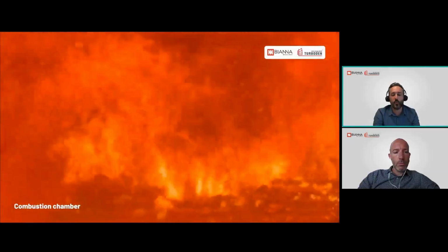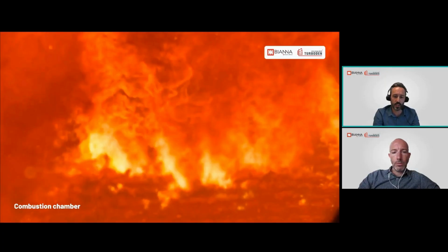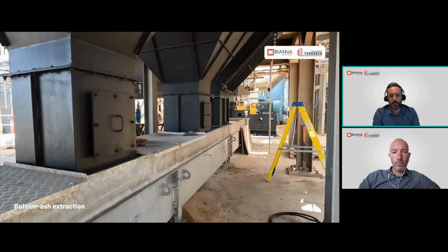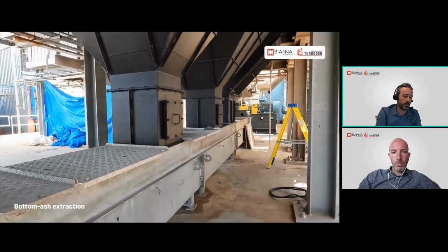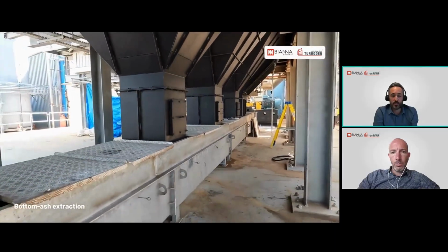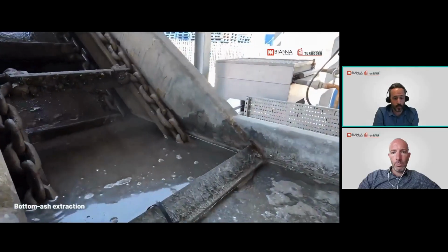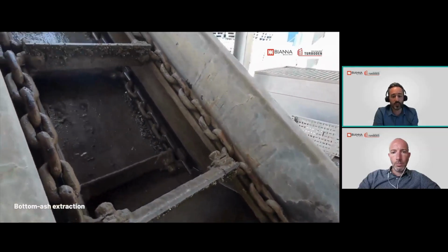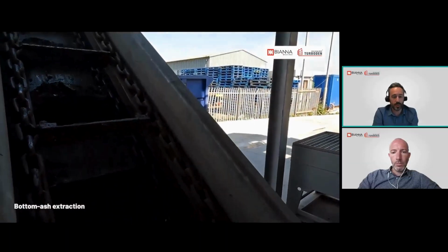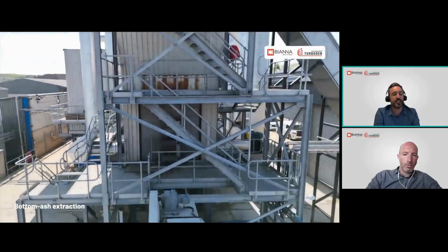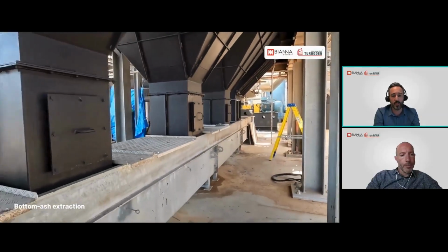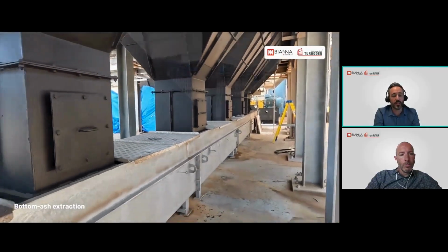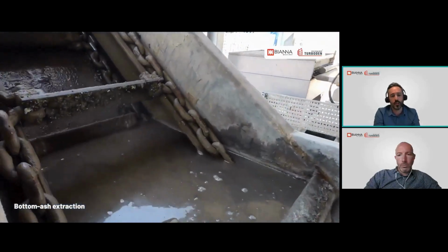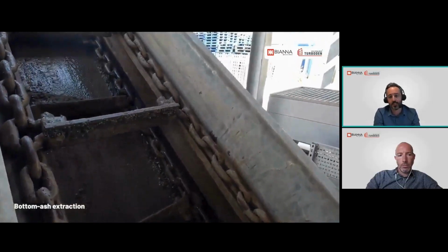So we can control the flame front, and also we can control how much unburned RDF could come into the de-ashing system. And talking about the de-ashing system, we go to the bottom ash extraction. As I already explained to you during the Horizon boiler video, one of the challenges of RDF is the high amount of inert and unburned particles. That's why we have selected a very strong system, able to manage up to 25 to 30% ashes. The bottom ashes are the ones that we are collecting from the combustion chamber. And as you can see, it has a chain which is submerged in the water, and it's able to drop the ashes into a single point.